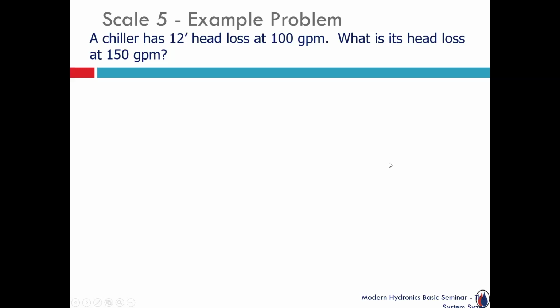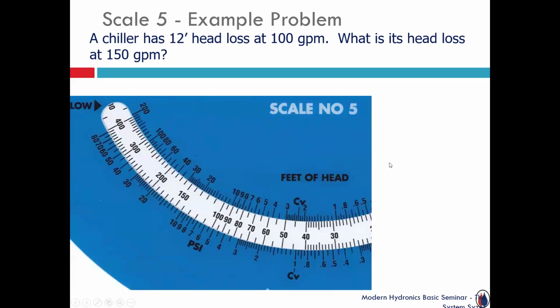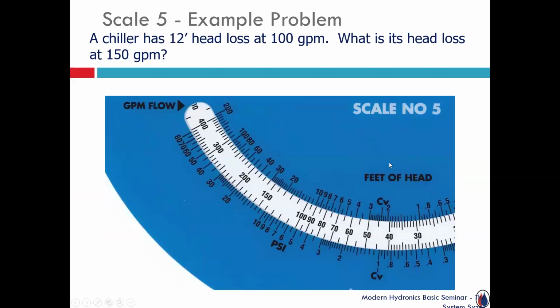So, real quick example, I've got a chiller, and the chiller manufacturer says, hey, when you move 100 GPM through my chiller barrel, I've got a pressure drop of 12 feet of head loss. And the question is, if I want to increase that flow through that chiller, what's the new pressure drop going to be? If I'm moving from 100 GPM to 150, can I calculate it? And the answer is yes, you can. Or quite simply, you can just take that scale, either on your app, on your phone, or the wheel itself.